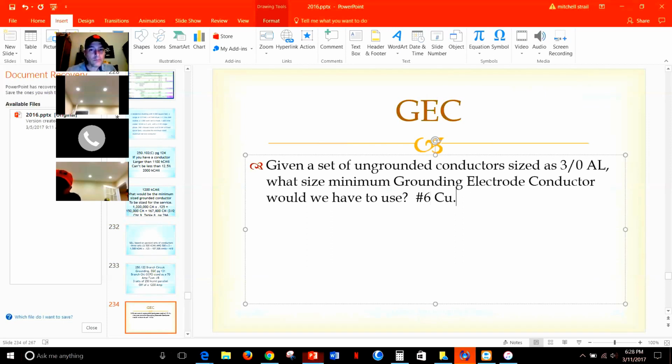I guess it's a stupid question, but when you're pulling, I know you said they use that rule of thumb because of copper, but usually when they pull aluminum, you do that, number 1, because of cost difference. Why would you assume that it would be the copper when you do the ground when they ask for aluminum? Here's the answer to that. It's a really good question, okay? I'm not saying that in the real world we might assume one way or the other, but a lot of times we run copper GECs anyway, even if we run aluminum feeders.